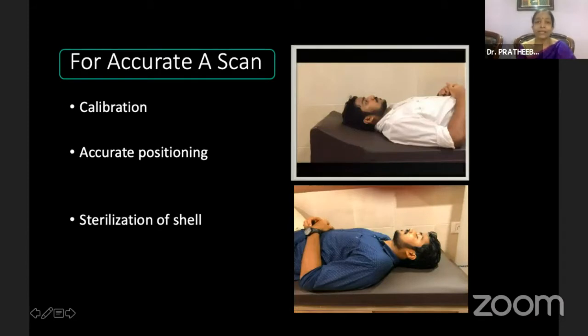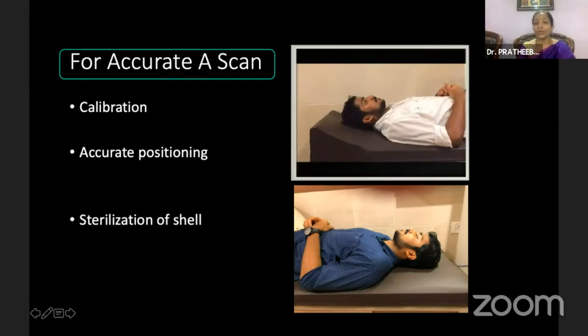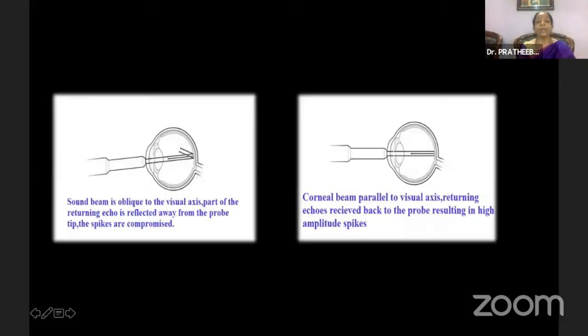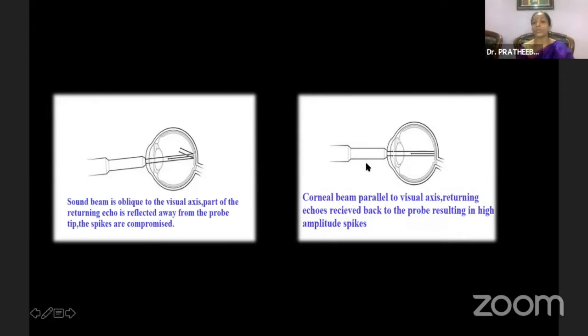For an accurate A-scan, proper calibration is mandatory, accurate positioning of the patient is very important, and proper sterilization of the shell is important. The patient must lie supine without any tilt — when there is head tilt, the sound beam is oblique to the visual axis, part of the returning echoes is reflected away from the probe tip, and spikes are compromised. When the patient looks straight, most echoes are perceived by the probe, giving good quality spikes and a proper axial length.